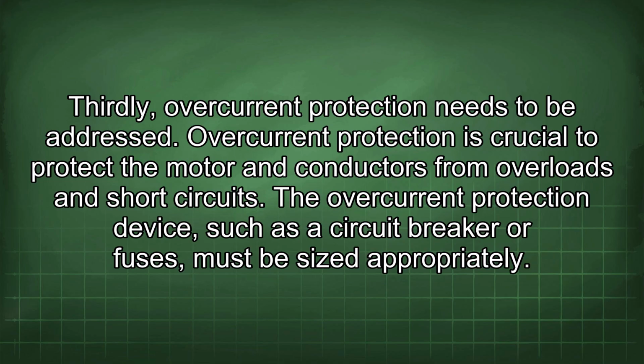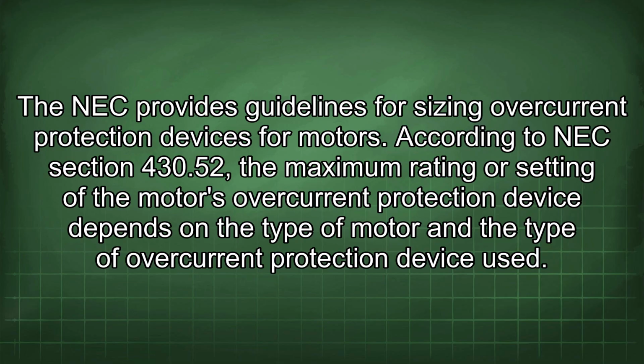Thirdly, overcurrent protection needs to be addressed. Overcurrent protection is crucial to protect the motor and conductors from overloads and short circuits. The overcurrent protection device, such as a circuit breaker or fuses, must be sized appropriately. The NEC provides guidelines for sizing overcurrent protection devices for motors. According to NEC section 430.52, the maximum rating or setting of the motor's overcurrent protection device depends on the type of motor and the type of overcurrent protection device used.